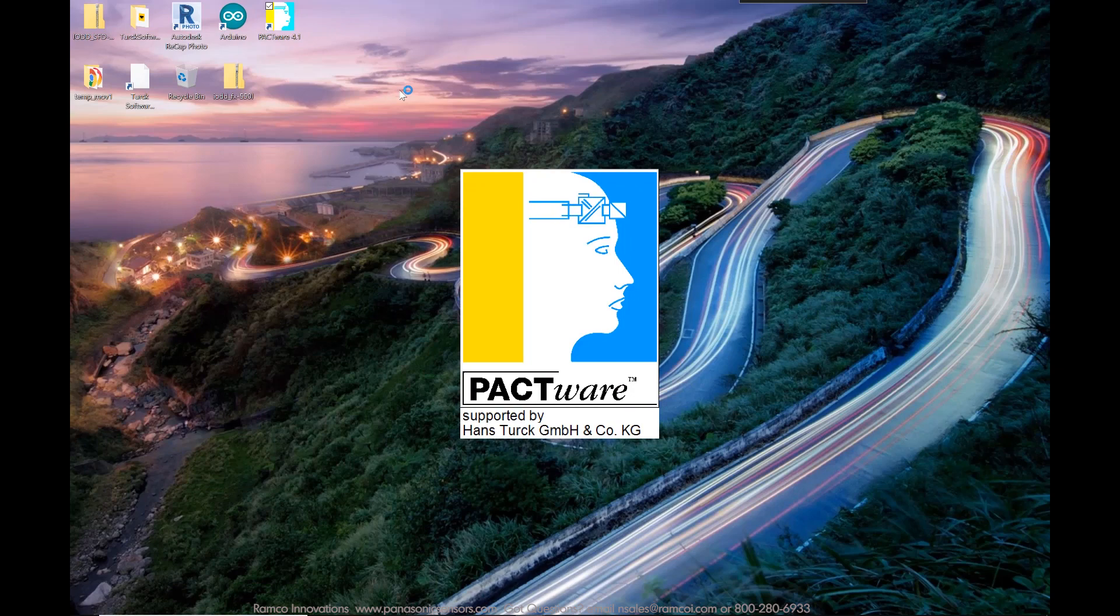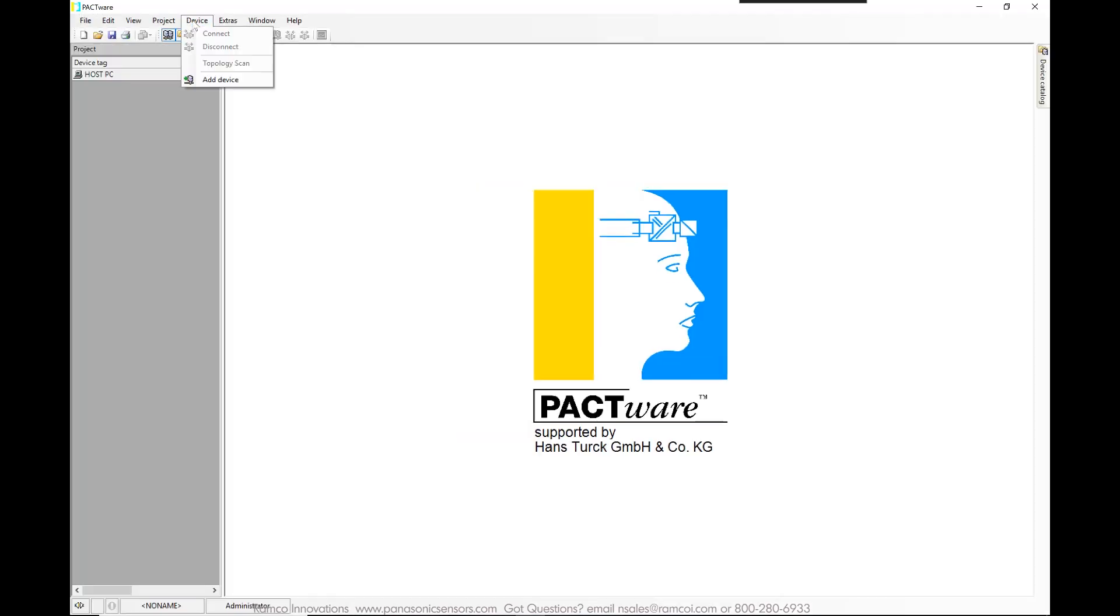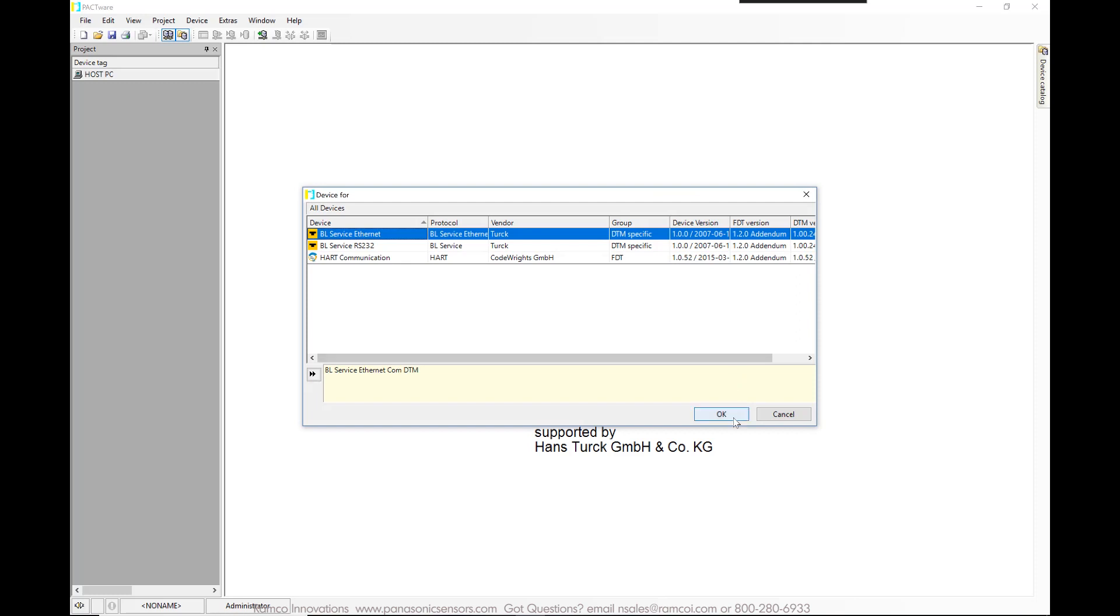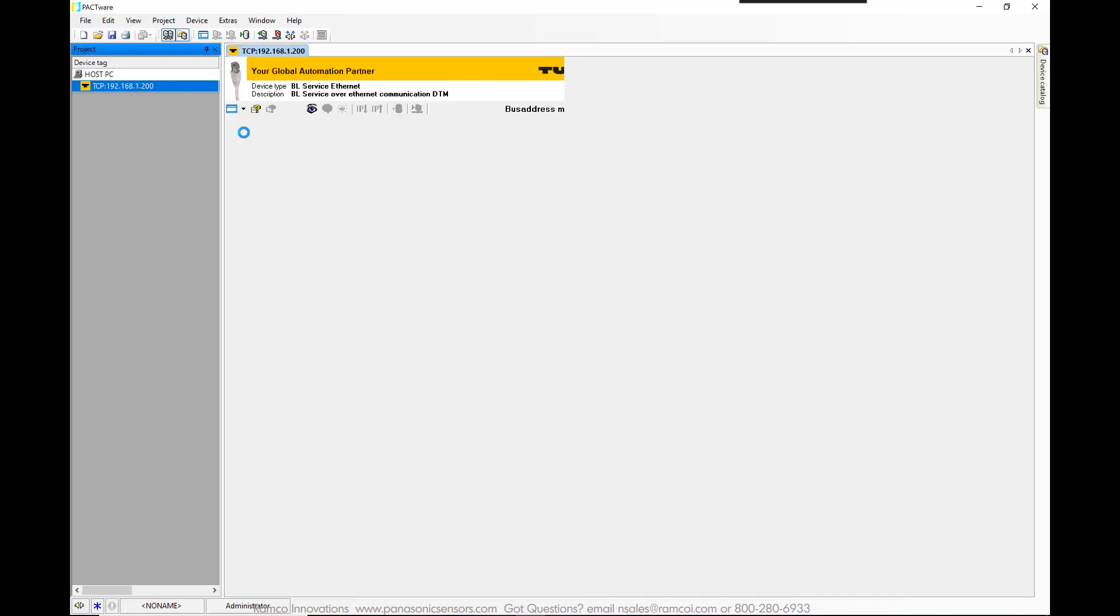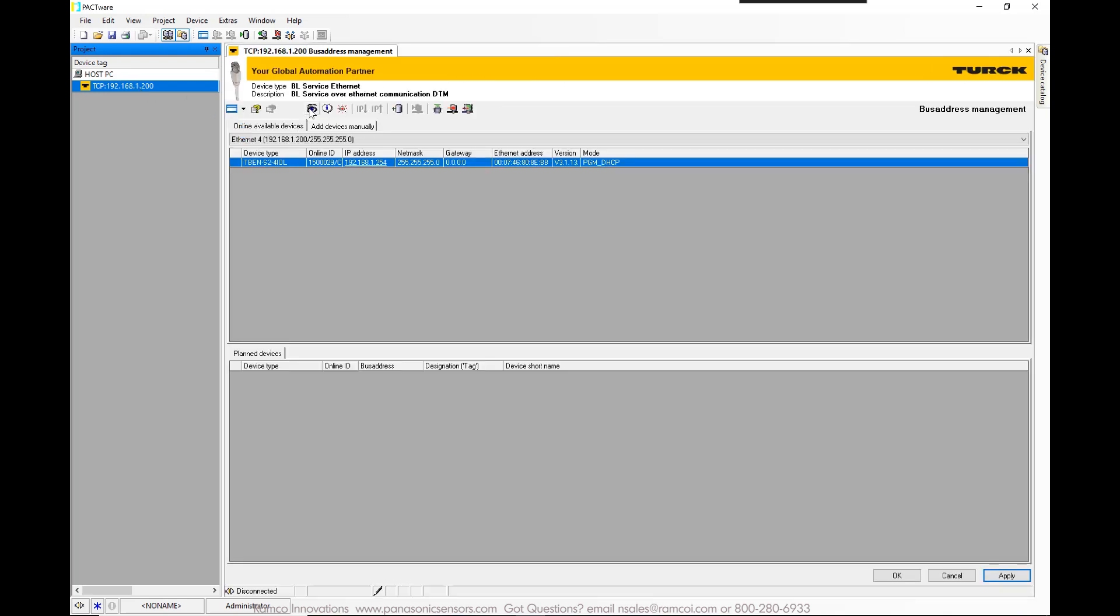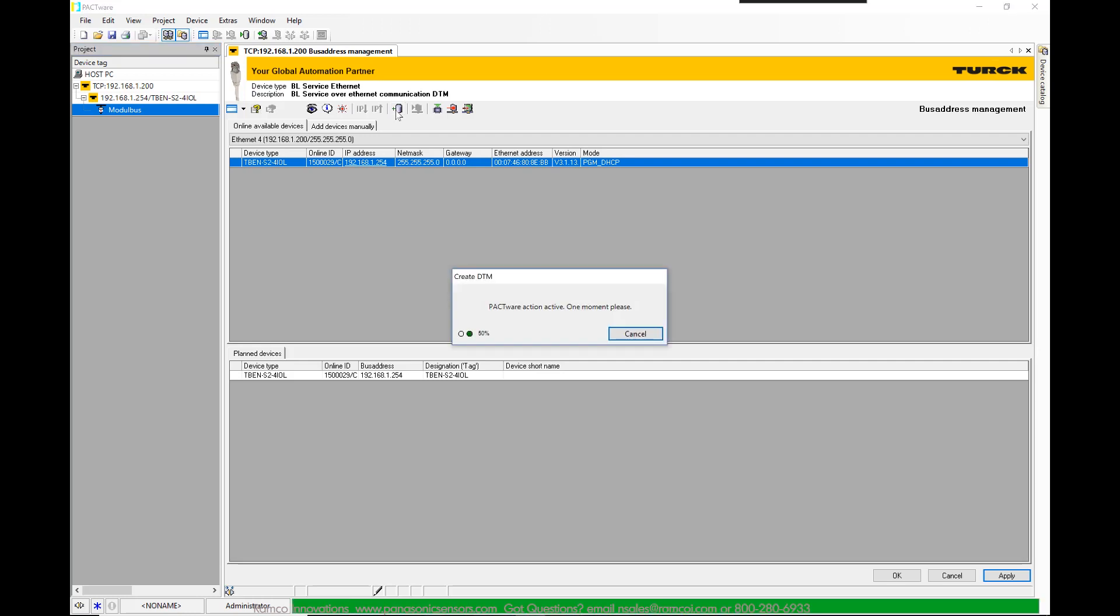To make it simple, I chose to demonstrate showing the sensor data by using PACTware software. PACTware is a manufacturer and field bus independent software for operating field instruments. In order to display and make changes to the parameter diagnosis and process data, you have to download the IO-DD files. Simply put, they are device description files for all of the IO-Link data from the sensor. This video is meant to give you a basic idea of how to set up IO-Link sensor with Turck block and PACTware software.